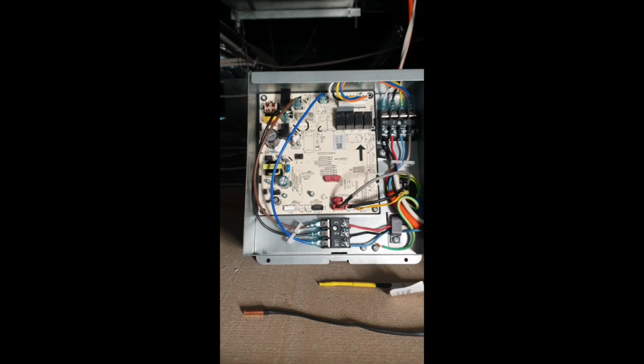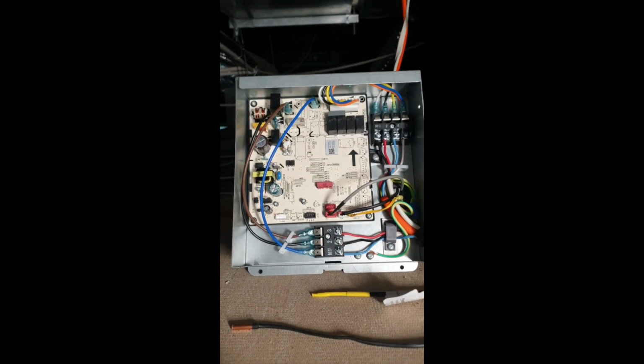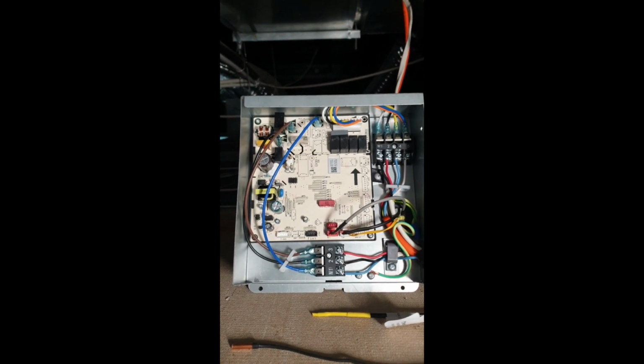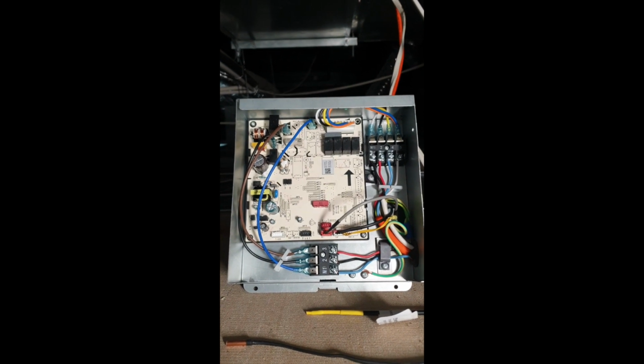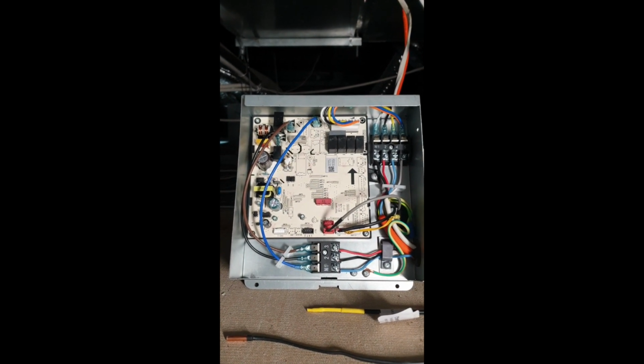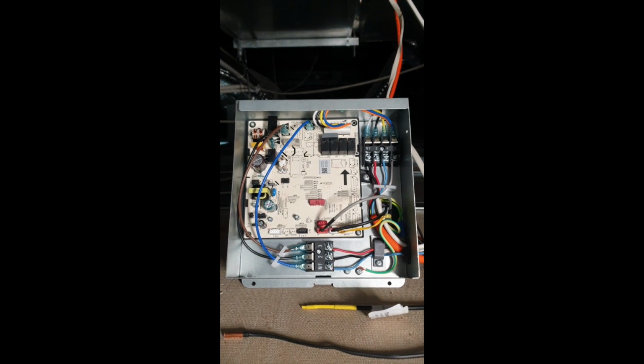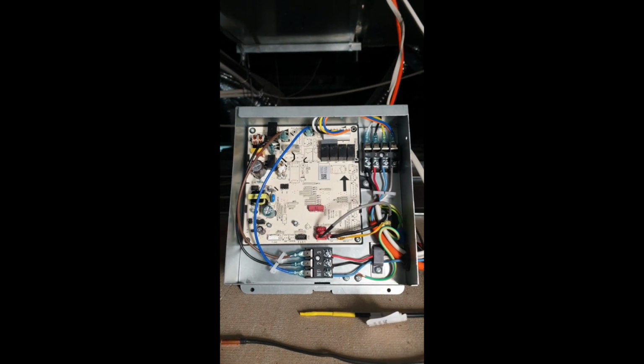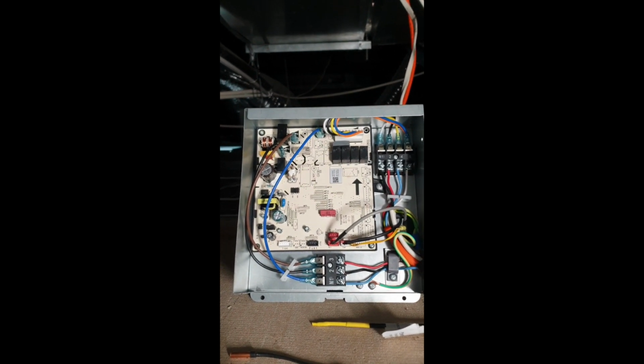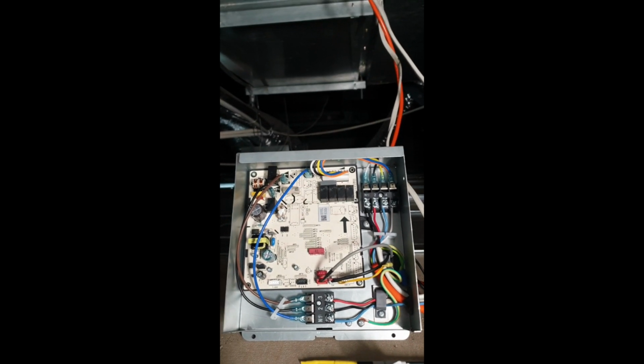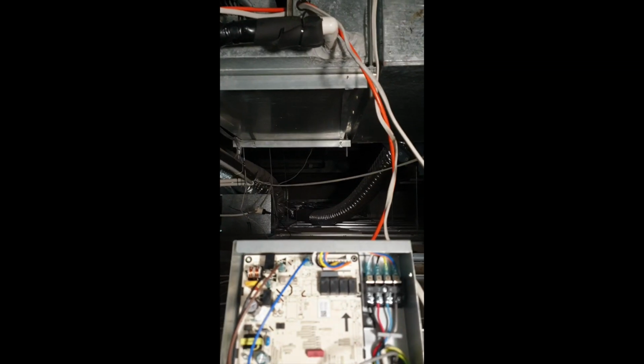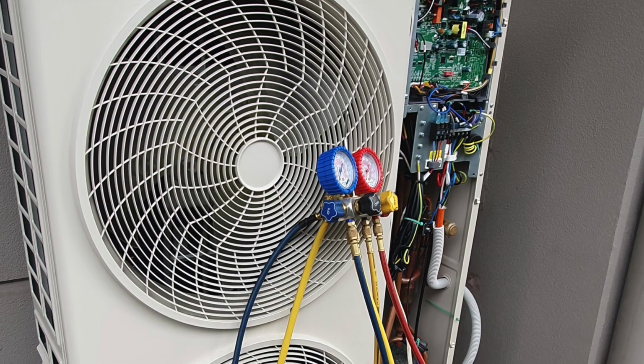These systems can be used either on hydrocarbons, very, very efficient, or 410A if that is what's required by the contractor. However, with using 410A, significant reduction in efficiency of this machine occurs. Our preference is hydrocarbons, of course, because they're pretty smart, pretty efficient. So that's it. Indoor unit remains where it is. The pipe work remains where it is. No disruption to the tenant. That's the tenant somewhere. And that's it. We'll come back in a moment and look at commissioning of the outdoor.